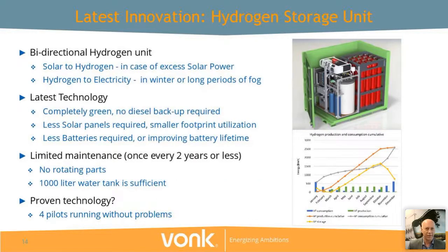I come now to a very new innovation that we add to the hybrid power system: the hydrogen storage unit. It's a nice system to complete your setup or add to your HPS. What it does is this: on good solar days during summer, spring or autumn, the batteries are already full by about 10 or 11 in the morning. The excess energy you produce, which you don't need for your loads, can then be sent through this system and converted into hydrogen that you can use in wintertime.